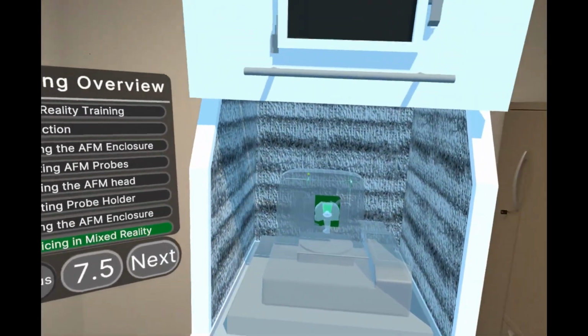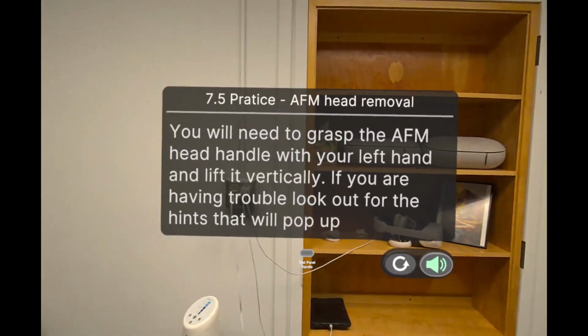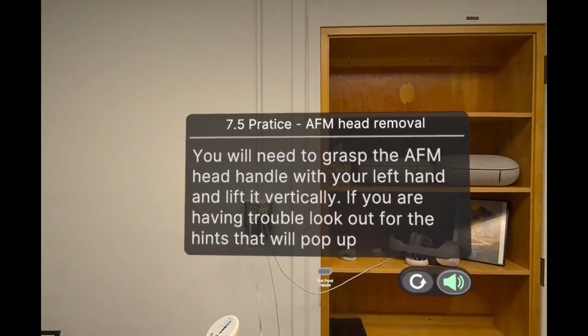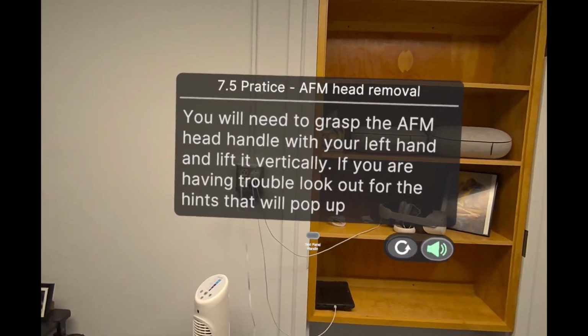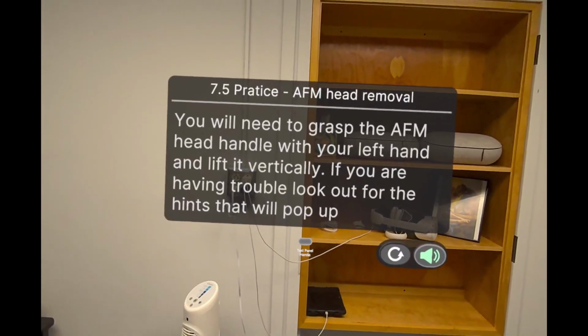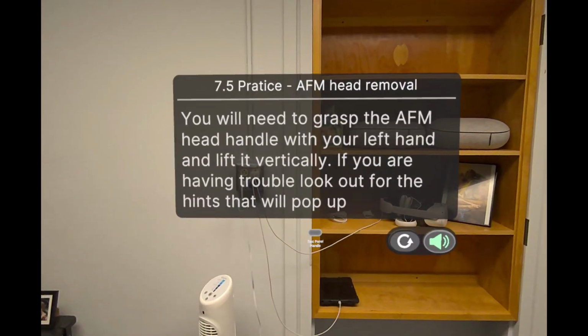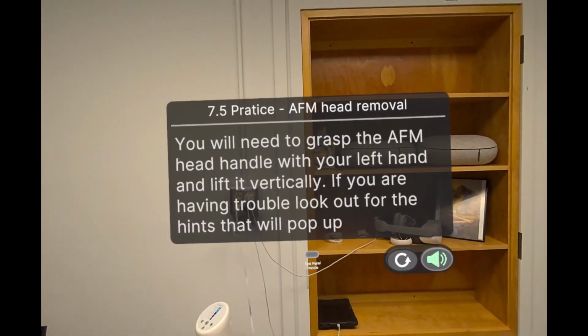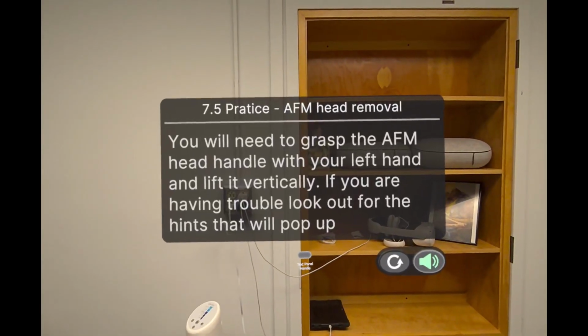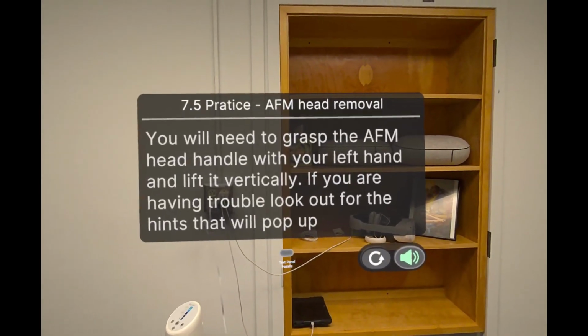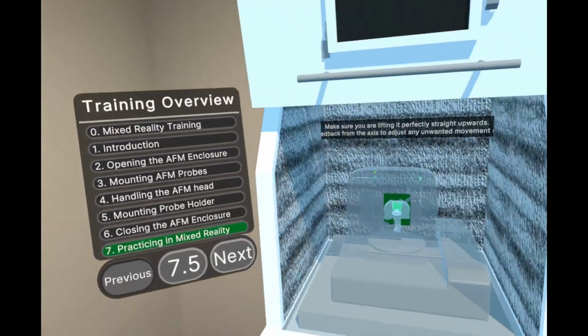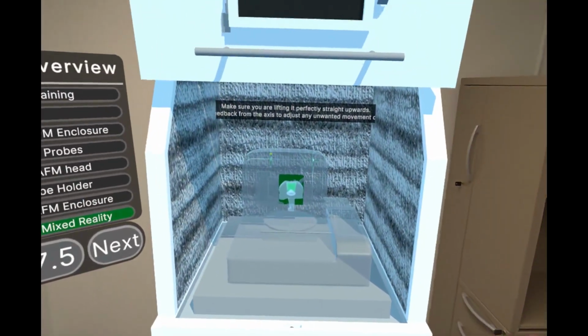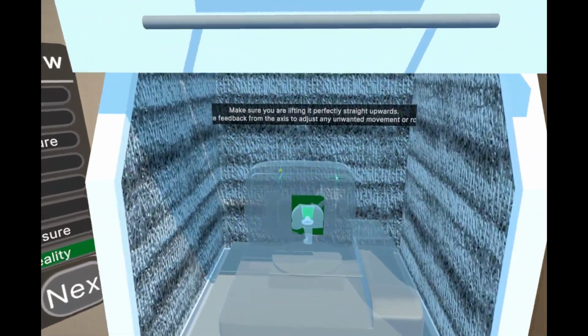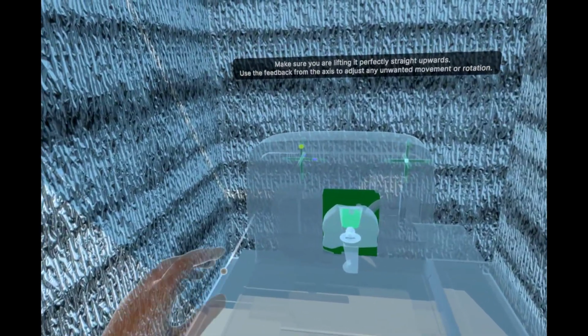Lifting the AFM head is the hardest part of learning to set up the icon. For this task, you will need to grasp the AFM head handle with your left hand and lift it vertically. The AFM head will not move if you are introducing any unwanted motion or rotation, so pay attention to the floating coordinate axes that provide feedback on how you are moving the AFM head.